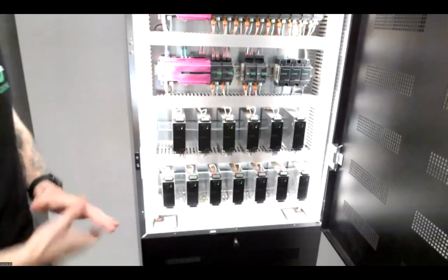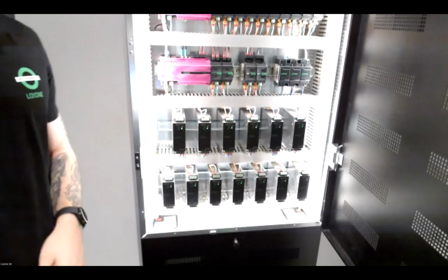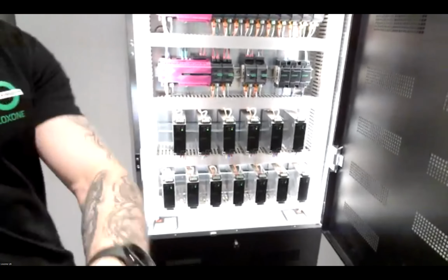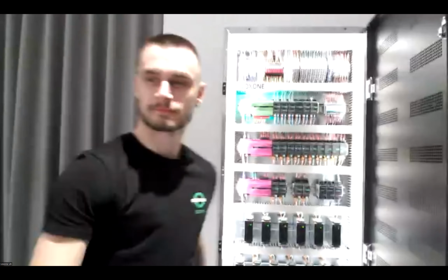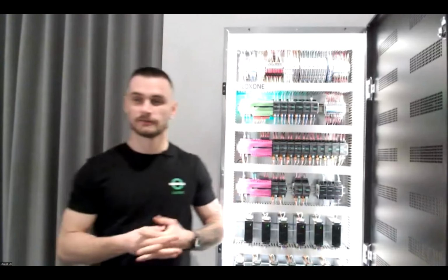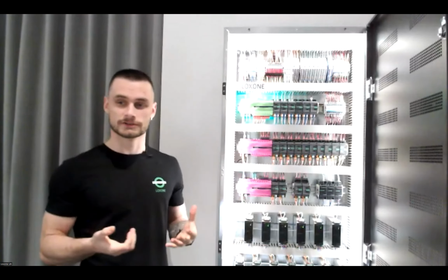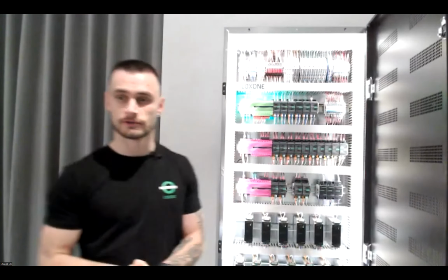Now, 130 amps or 135 amps is what we specified initially. And this is exactly what we thought is going to be necessary to get everything up and running. However, after sitting down, recalculating everything, talking internally with the team and seeing what we can do to improve the whole situation, we found out 135 amps is actually never going to be used.